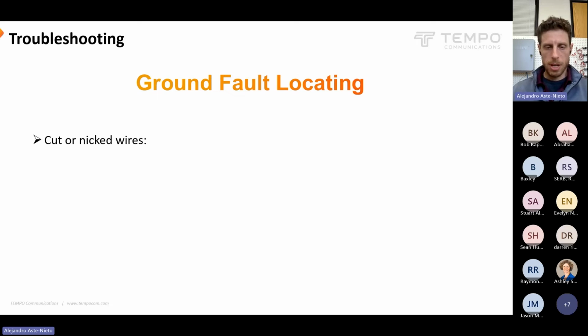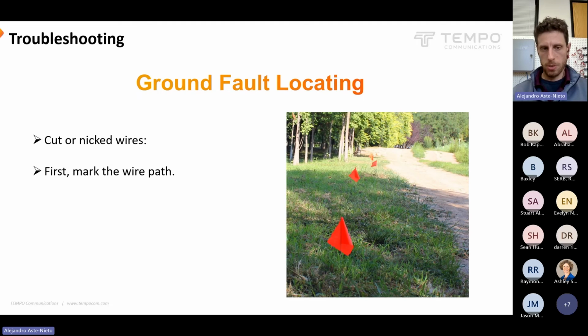So if we have a ground fault, it's usually going to be near a valve box. It's usually going to be a splice issue or a nicked wire from when those wires were stripped. But maybe the wires got nicked when somebody was digging somewhere between valve boxes. If that's the case, we can find where that's located using our ground fault locator PE 2003. Just make sure that you know the route of the wire path. That'll make it a lot easier.